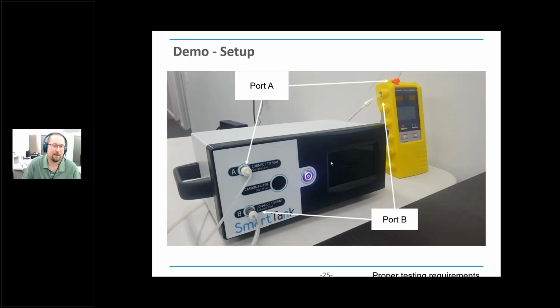So real fast on this demo today, there's the way we have it set up. I've got this little yellow device, which is a microstream. It's the same technology that's in the Philips 3015A. I've got port A hooked up to this orange sample line, and I'll have the exhaust port over here on this device connected over here to port B. We do that on certain devices. We can actually do a leak test that we developed. That's a lot faster than a leak down test and does a really good job. But the SmartTank can also do a leak down test, but today we'll show you this method.